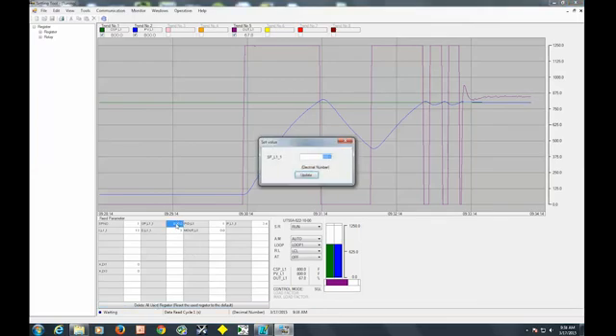Very simple process. This is a very good tool when you're tuning. You can actually do manual tuning here as well. We can go in and tweak the PID settings if we're finding that the process, the PID settings for the process are a little too aggressive. We can reduce those to make our control even better. But from what you're seeing here, we didn't overshoot at all. Nice ramp down, and we're now maintaining 600 degrees. We're at 599.6. That's really all that you need to do to tune the loop to make it have the proper parameters for optimum performance.